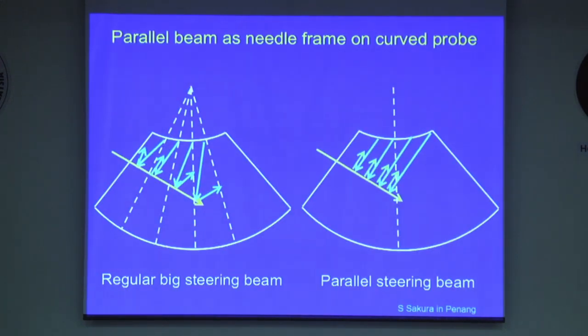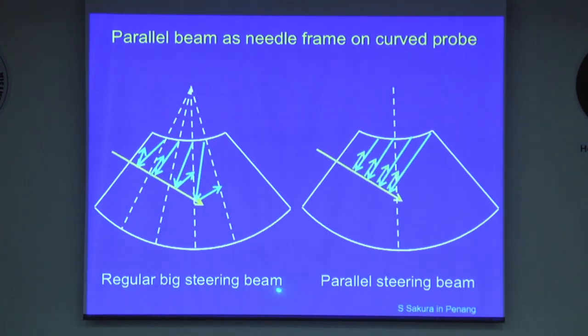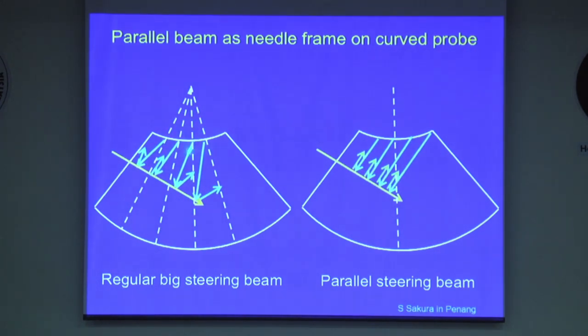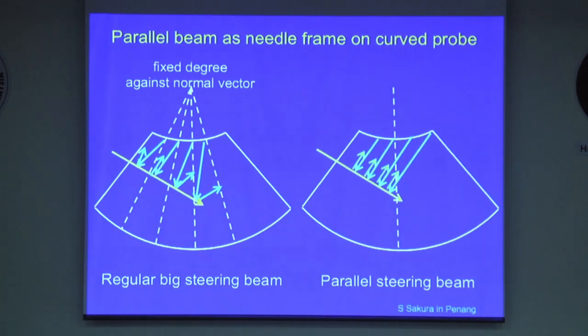For curvilinear probes, there is another technology. The left-hand figure shows the regular beam steering. With this, you can see the needle beam, and each needle beam has an angle of a fixed degree against the normal vector — meaning vertical to the surface.